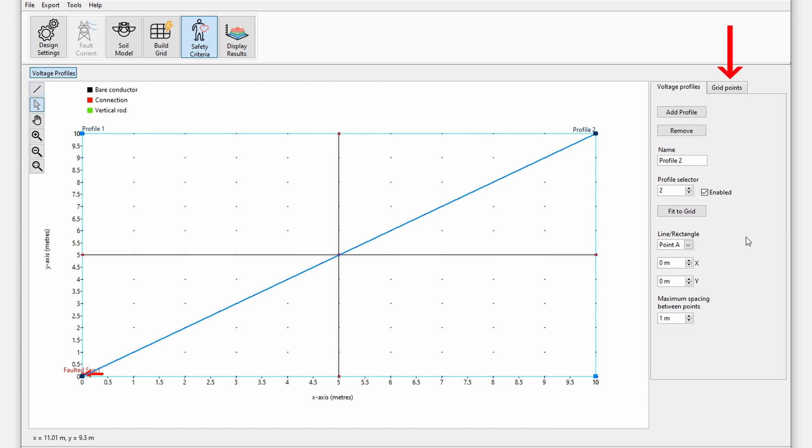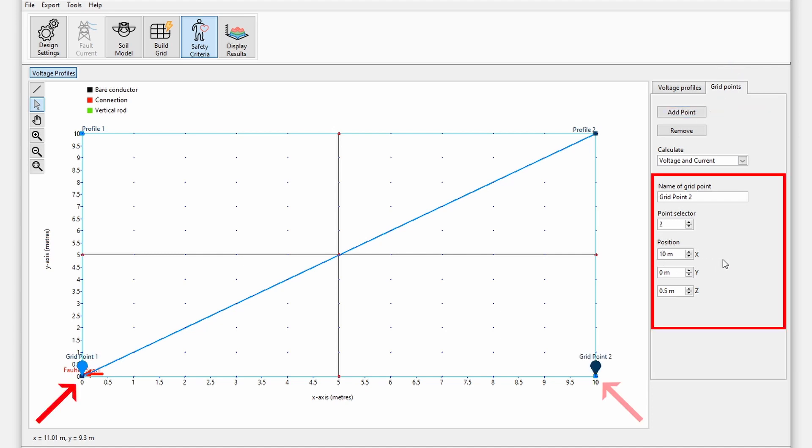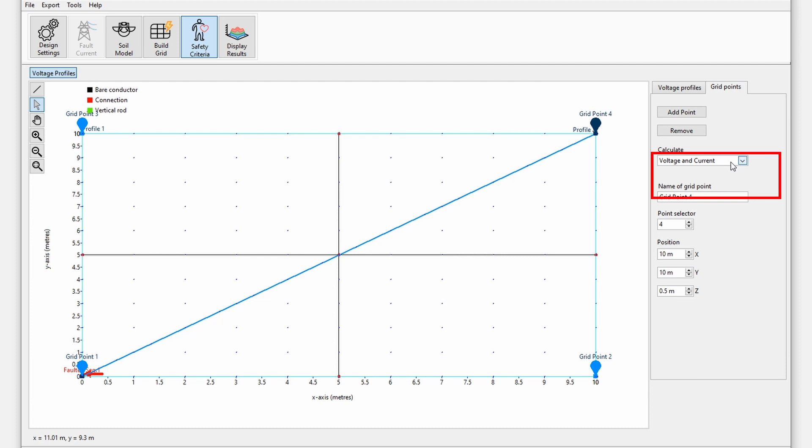Next, go to the grid points tab and add 4 grid points and move each grid point to a corner of the grid using the mouse. Grid points measure voltages and currents on the conductors. Note that any number of grid points can be added and that their locations will automatically be snapped to the grid conductors during the calculations. Set the calculate mode to voltage and current for each of the grid points.